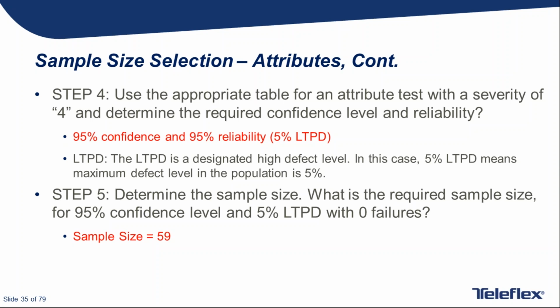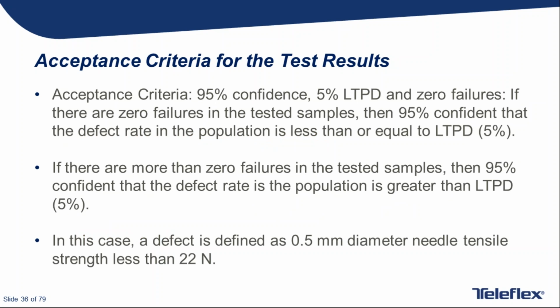So the severity level of 4 corresponds to the 95/95 confidence reliability and a sample size of 59. And I just want to mention the term LTPD here, as I did before. This is a common sampling term and is another way to measure how well we protect the consumer. And LTPD is basically the inverse of reliability. 95% reliability is 5% lot tolerance percent defective. So we test 59 and allow 0 failures, and it can be pretty clear cut. None of the samples would be allowed to have a tensile strength less than 22 newtons.